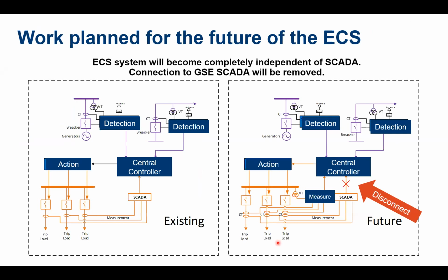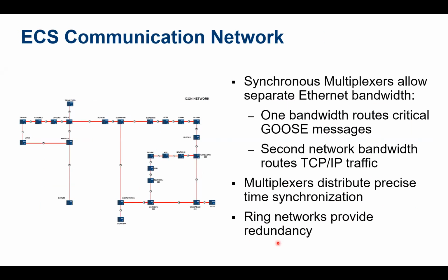Eduardo, excuse me, may I say a few words, just a few words about the ECS communication network, which is based on SEL ICON multiplexers. Yes, please. This communication network in GSE is used for the protection grade systems. The SCADA system has another multiplexer network, an SDH multiplexer network. This is one more reason why we decided not to combine the SCADA HMI with the ECS HMI.